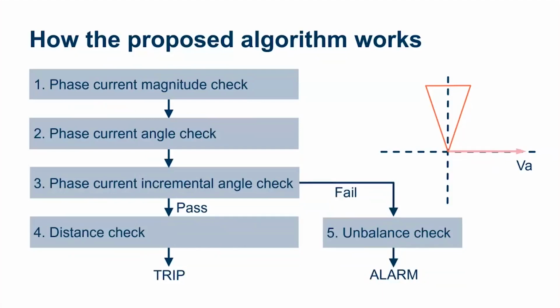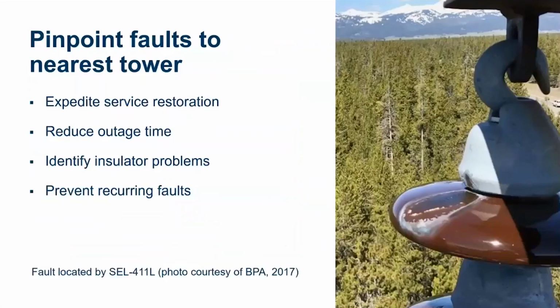Next thing I'm going to talk about is fault location. How we're going to attempt to mitigate wildfires using fault location is using traveling wave fault location algorithms, the double-ended traveling wave method. What we can do with that is pinpoint the fault location within a tower span, so that if there is a fault, we can hopefully expedite service restoration and reduce outage time. If we've got a damaged insulator, like is shown in this figure here, we can hopefully identify that and replace the insulator.